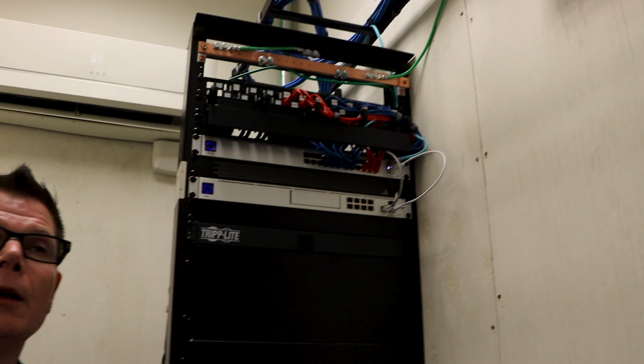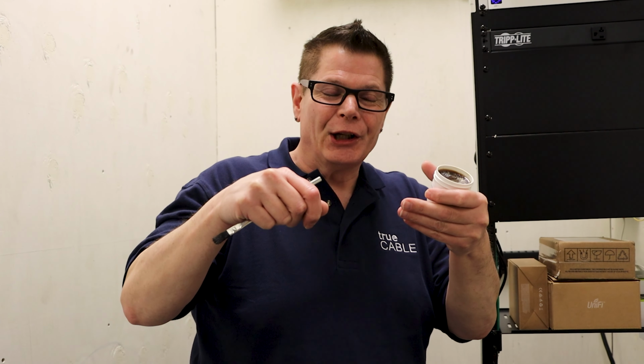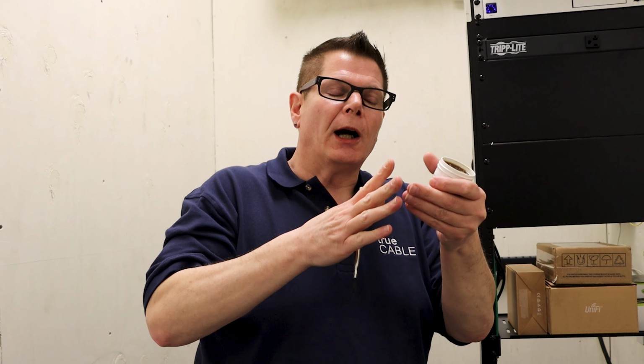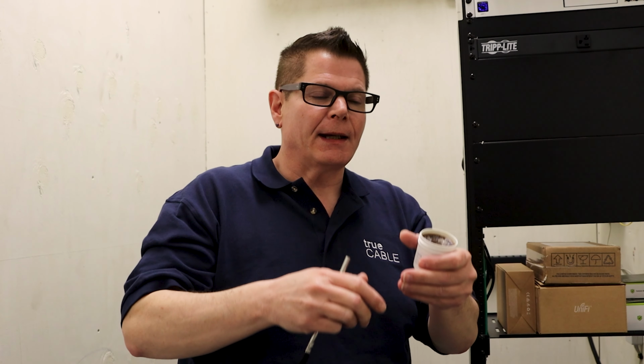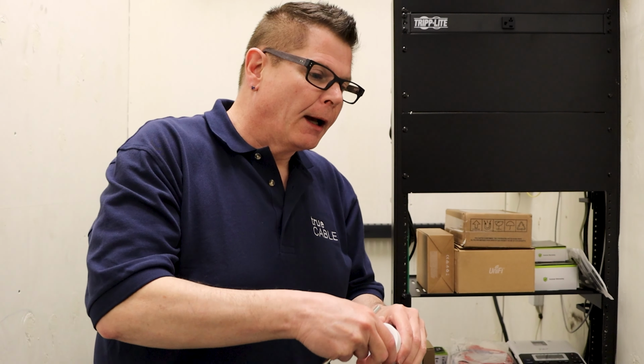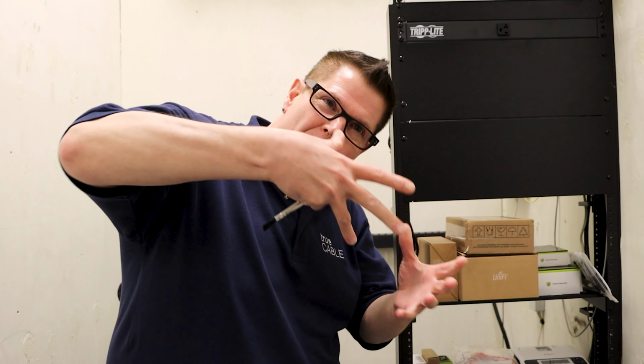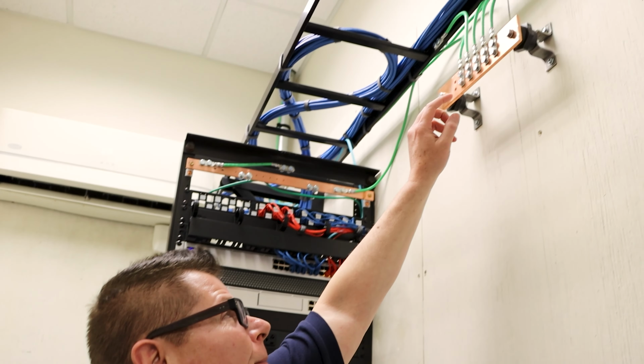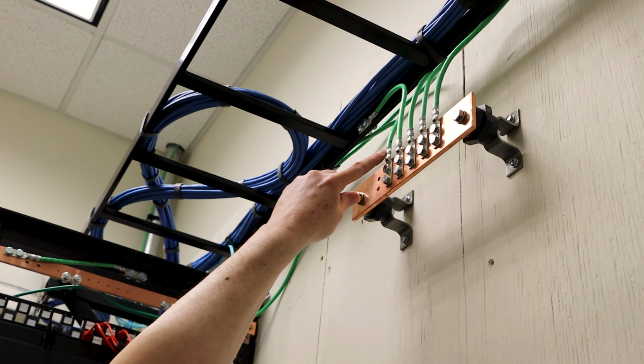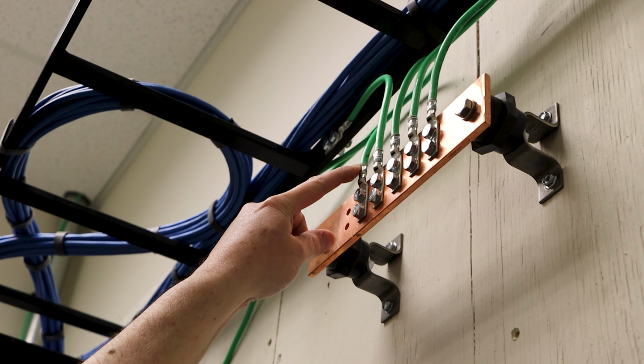When you are terminating your lugs onto the 6 AWG solid copper or stranded copper bonding conductor, you are crimping it in two places, and it requires a special crimping tool which I don't have here to demonstrate for you at the moment. But it does require quite a bit of force to crimp one of these lugs down. And as you can see, they're really crimped down there good. They're actually crimped in 2 places.